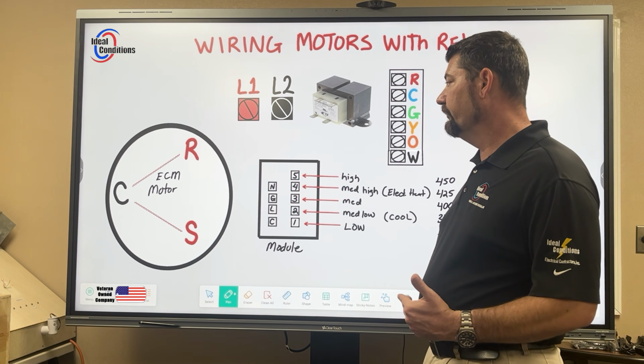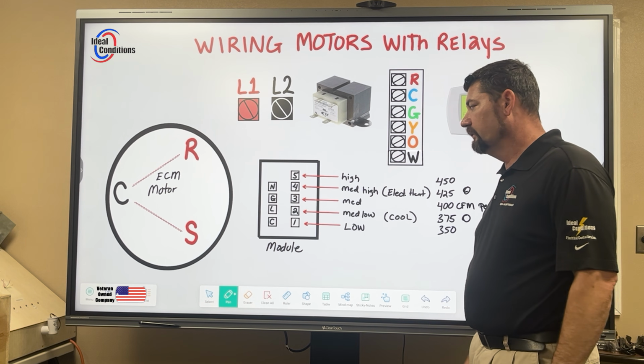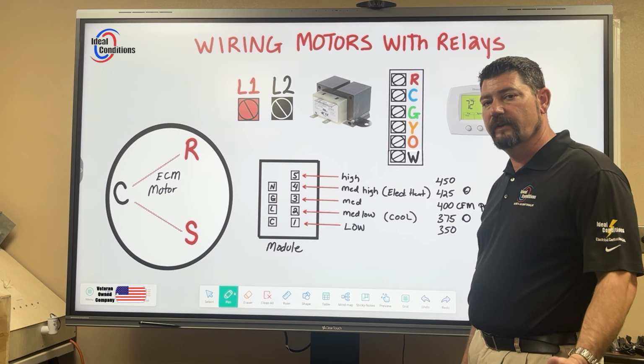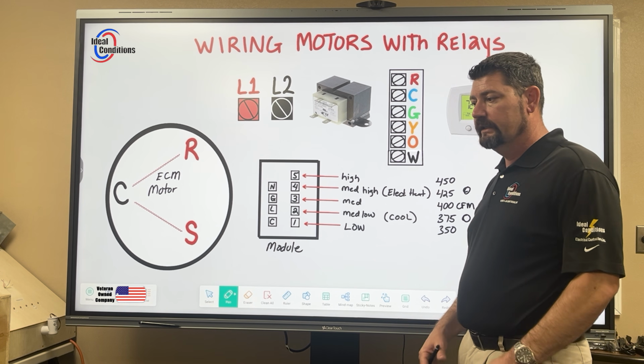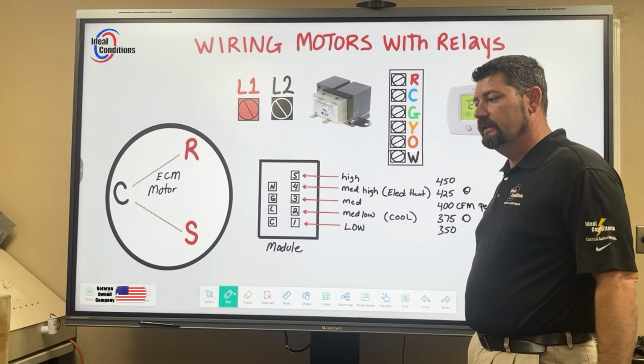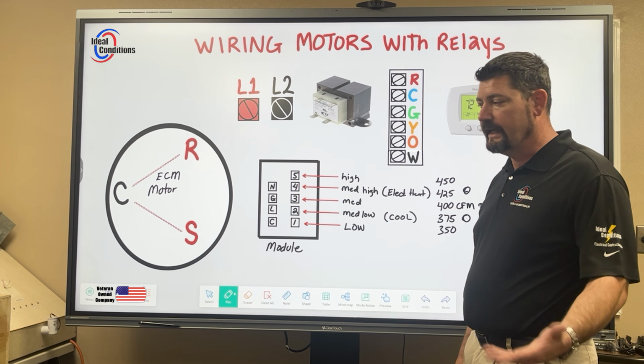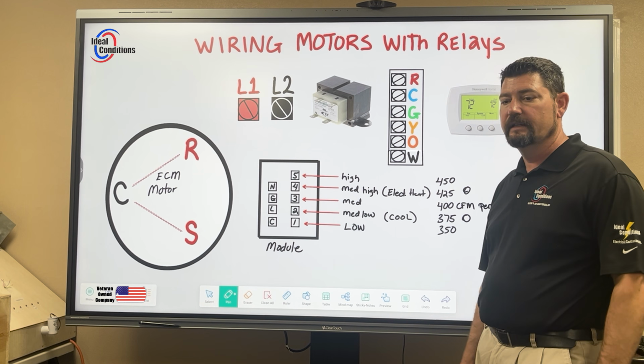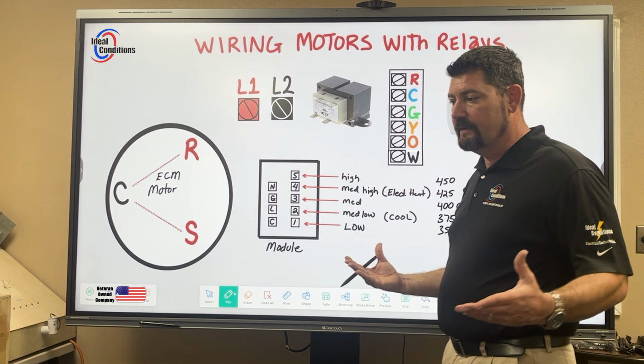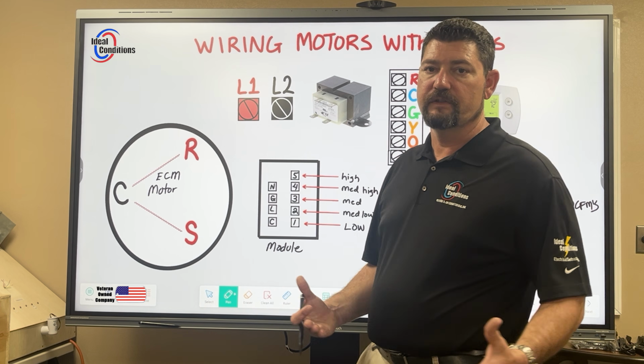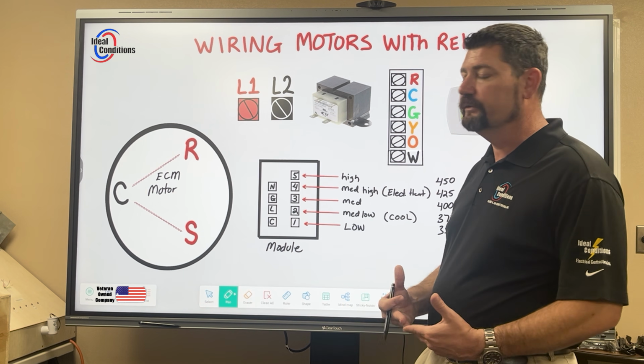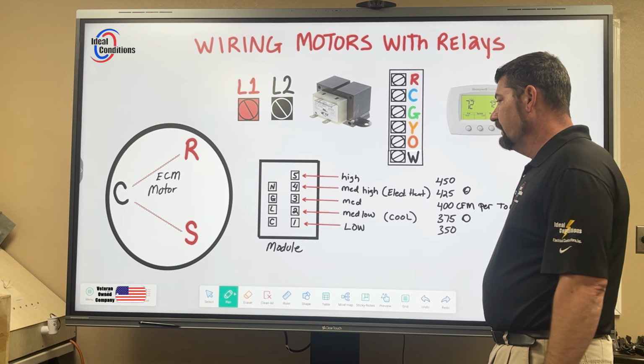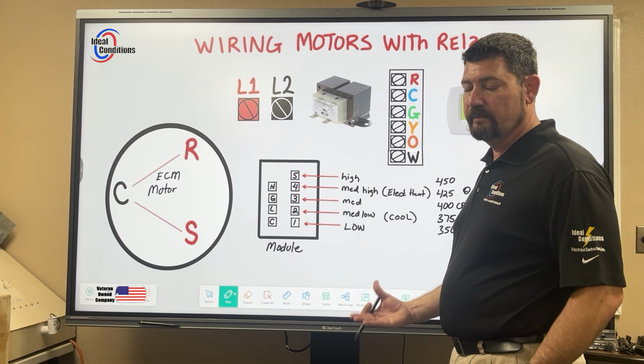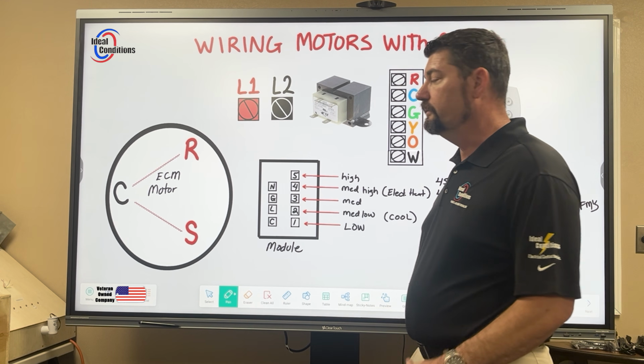Typically when your motor fails, it's a little bit more serious, but they do fail too. Caked up coils, that typically is going to kill the module. But I have seen plenty of motors go bad just because they've been running on too much resistance, and the windings just aren't built for that. So it's typically when you see that, the modules have been replaced a couple times and the motors eventually fail.